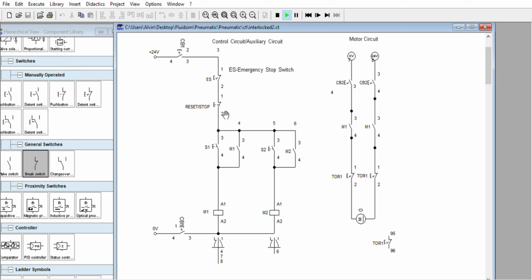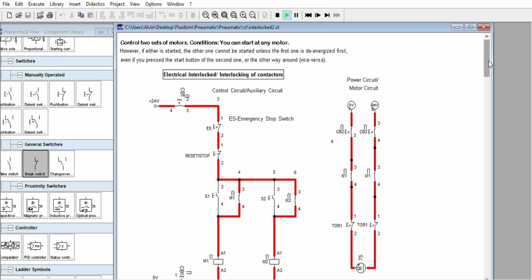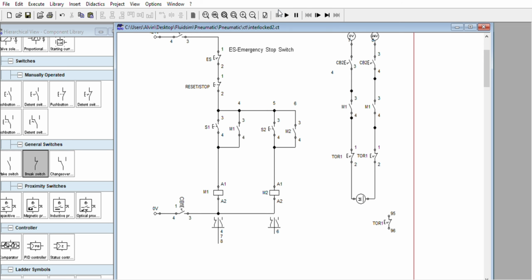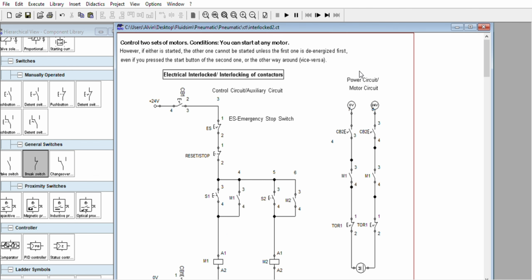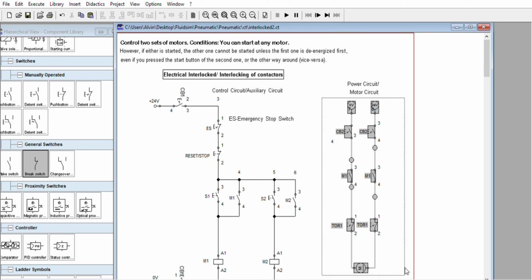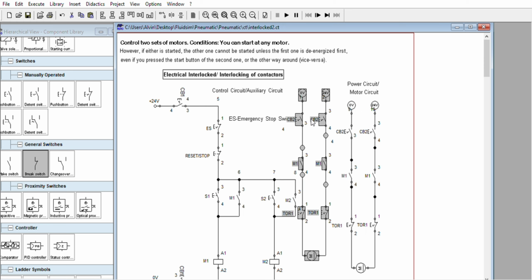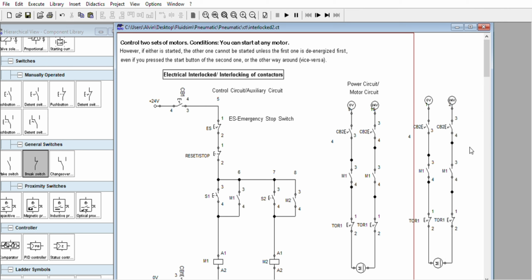See? They are functioning together. This is a problem because it is not the condition there. So electrical interlock is not yet present. If we are going to motor number 2, you just copy this one and change the power contacts to M2, power contacts M2, and let's say TOR number 2, or overload relay number 2, whatever is your preferred.